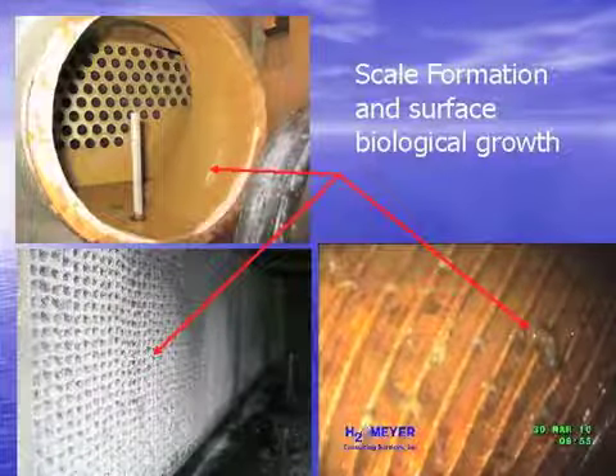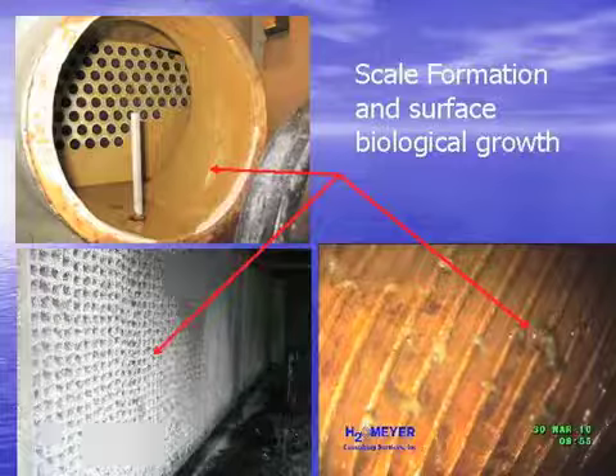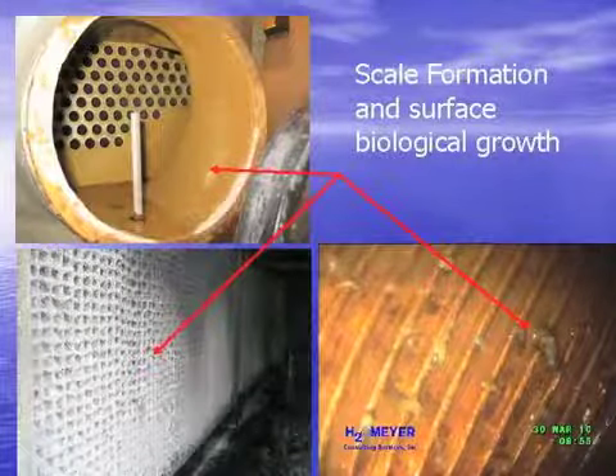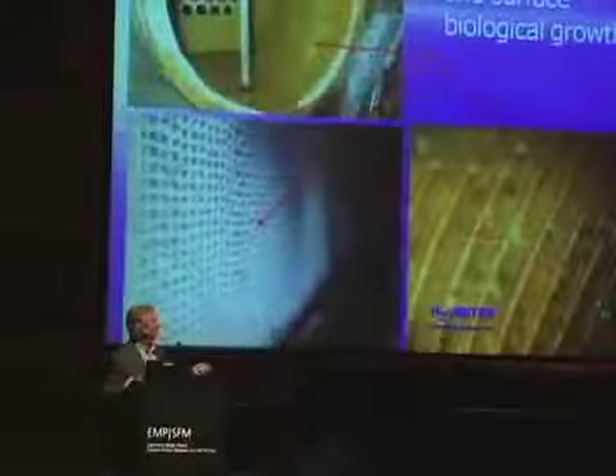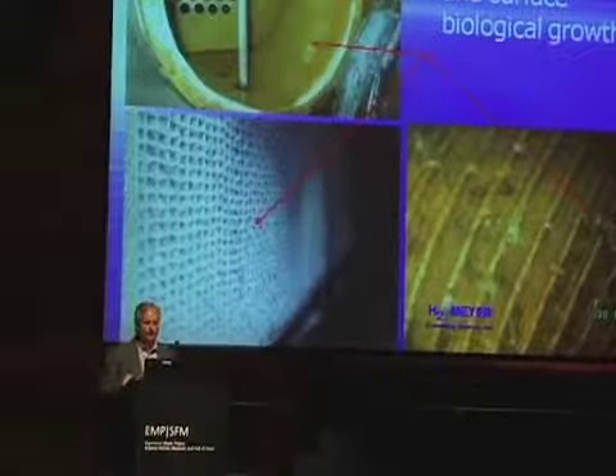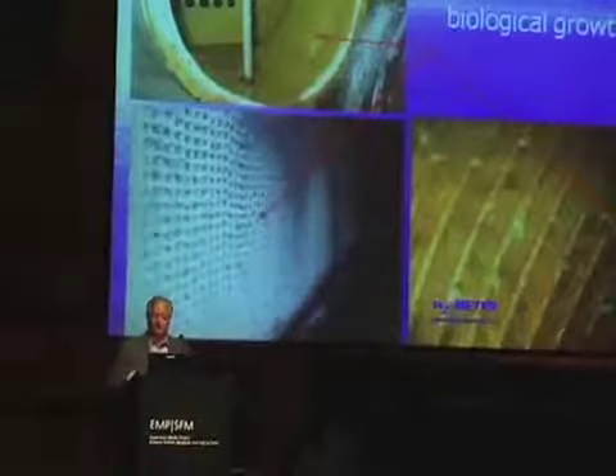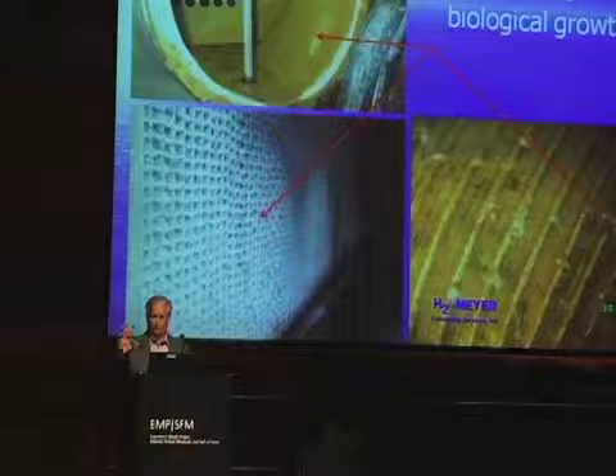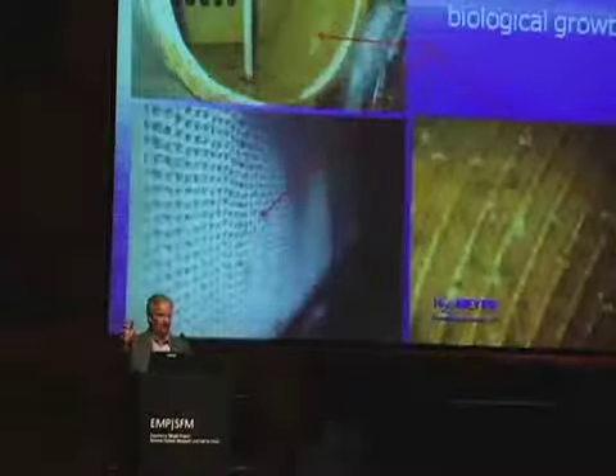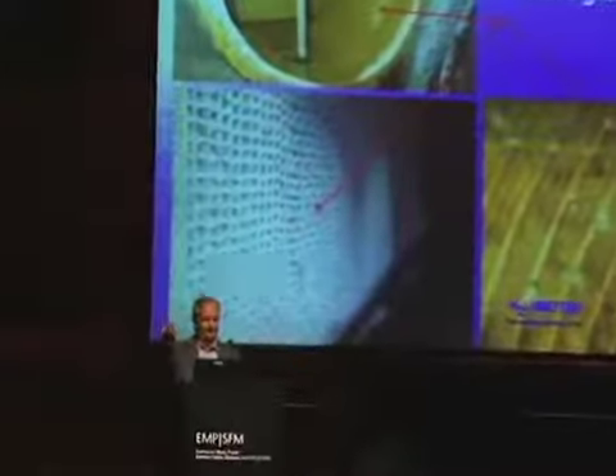If you exceed the limitations of their units, you can still see scale formation, just like you can with chemistry. So we've seen some towers with pretty high scale formation. The problem with some of these units is that it's a piece of equipment, so the light blinks on the wall. Everybody says the light's blinking, everything's working. Yeah, light's blinking. But unless you're doing some chemistry to make sure things are working, you don't know if the light's just blinking or if it's actually doing something. So you still need to run the test. You still need to do your maintenance behind some of these programs.